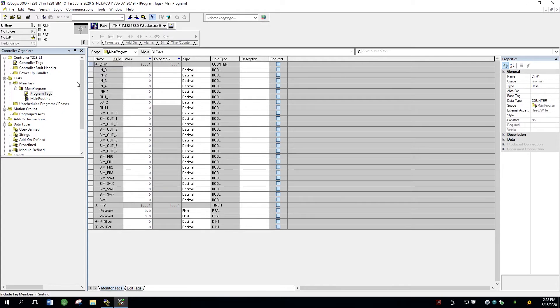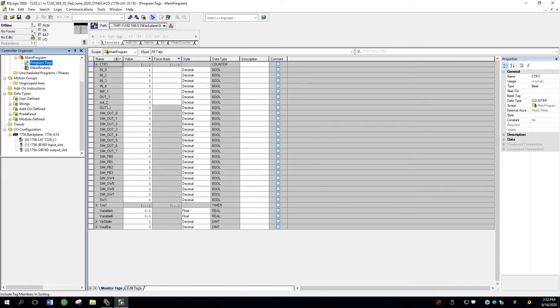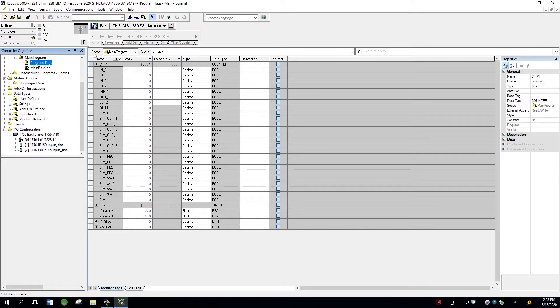So that seems to work. The other thing that I want to confirm here is that I see the three modules — or two modules — the input and the output and the controller, which is in slot zero. The input is slot one, output is slot two. The other thing that's important to check for is this IP address here — it's the communications path to the PLC, which is at 192.168.0.3. And this is for T228; CA219B is a little bit different. So go back to the main routine.